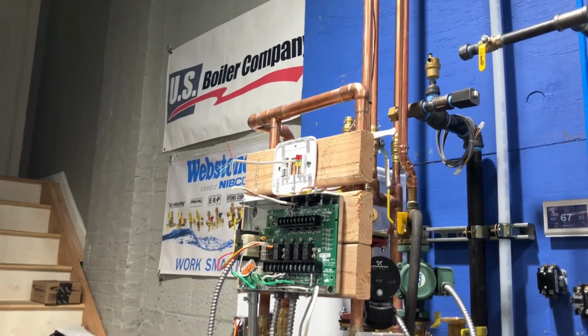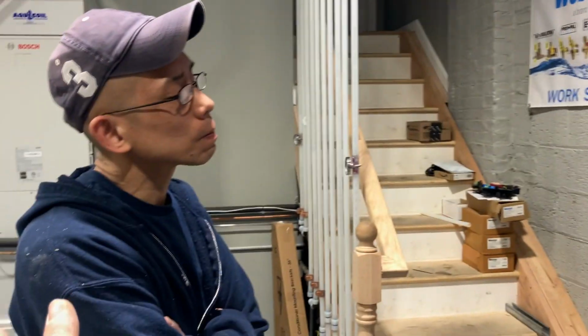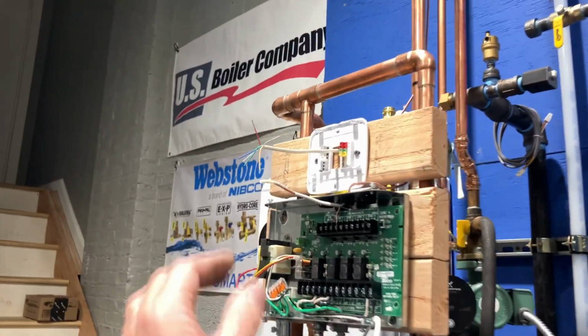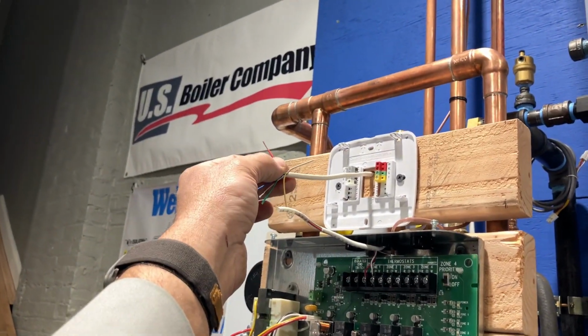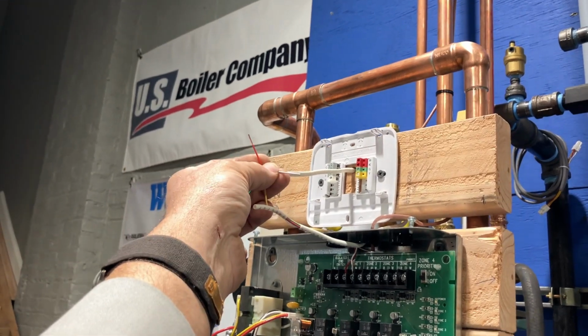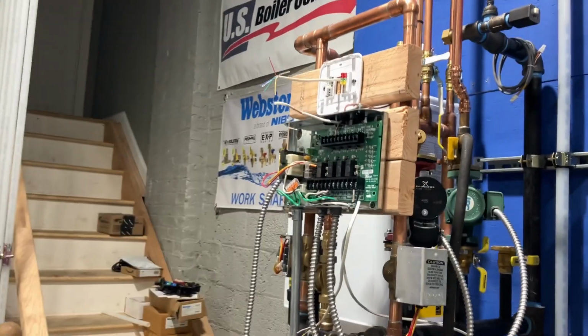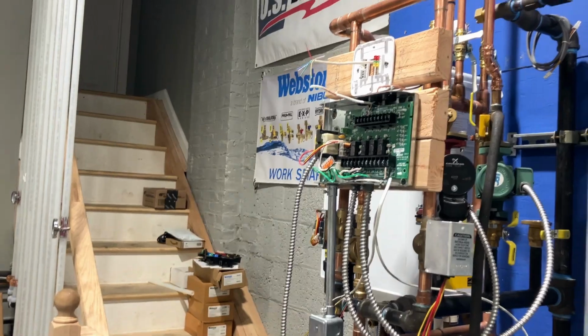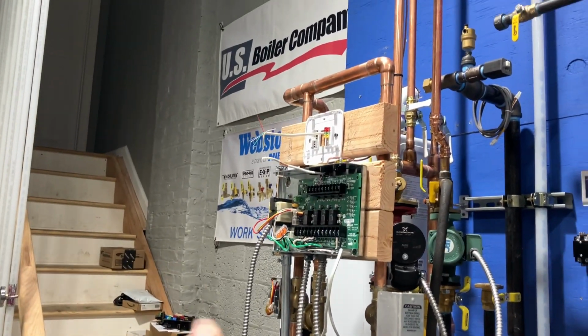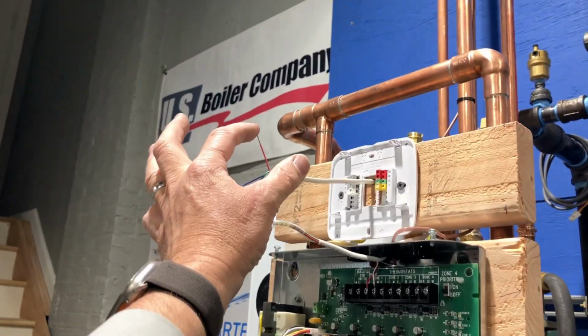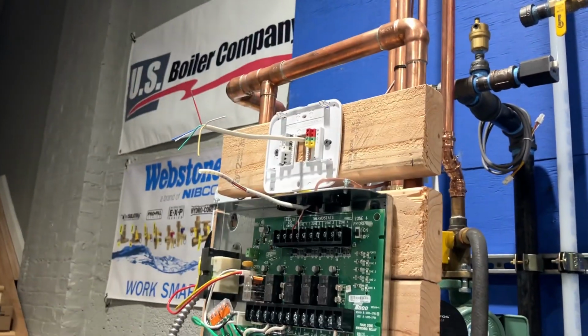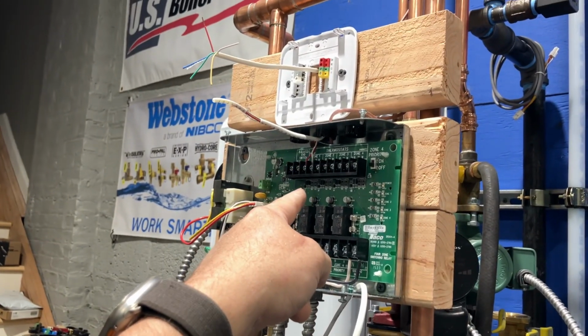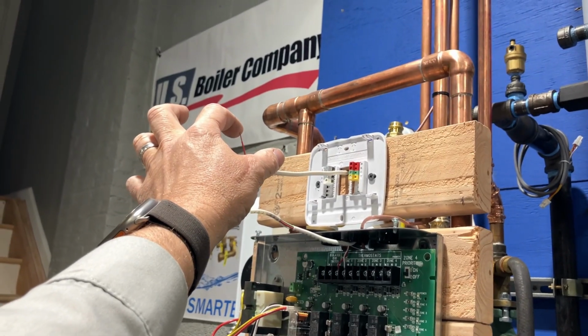That is the standard. Now, it could be any standard that you want to use in your head, but the industry standard is R is always the red wire, W is always the white wire. Okay? You can use anything you want, but you shouldn't, because you should stay within protocol and within standards. Whatever you use here, you need to use at the boiler or the zone relay. Okay? So let's use R and W.